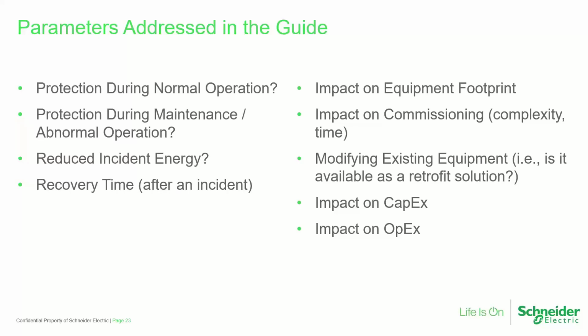Is this a solution that will reduce incident energy? We talked about how not all the mitigation techniques do that. We're also trying to give you some guidance on, if it does reduce incident energy, approximately how much. These are not values that you can quote us on, so to speak, but at least it gives you some rough idea. Are we talking about 8-calorie range, or less than 40, or less than 1.2? Where are we coming in?